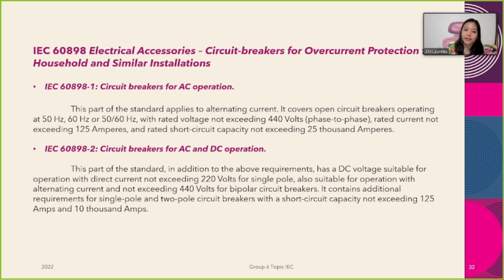Lastly, we have the IEC 60898, or yung electrical accessories for circuit breakers for overcurrent protection for household and similar installations. Alam naman natin na yung circuit breakers are automatically operated electrical switches na dinedesign para protektahan yung isang electrical circuit from damage caused by currents na nangyayari dahil sa overload or short circuit. So, meron tayong IEC standard, which is yung 60898-1 para siya sa mga AC operation. So, itong standard na to is nag-a-apply for alternating current, kasama na dito yung mga open circuit breakers operating at 50 Hz, 60 Hz, with rated voltage not exceeding 440 volts, and then rated current not exceeding 125 ampere, and rated short circuit capacity not exceeding 25,000 amperes.